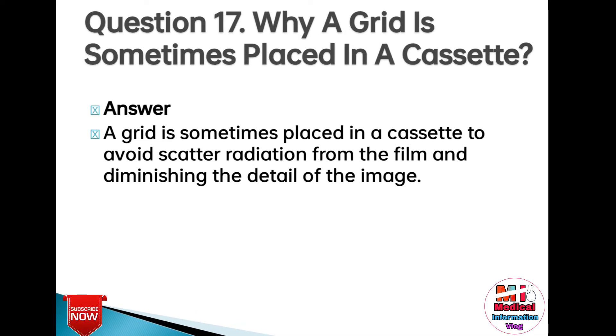Question 17: Why is a grid sometimes placed in a cassette? Answer: A grid is sometimes placed in a cassette to avoid scatter radiation from reaching the film and to prevent diminishing the detail of the image.